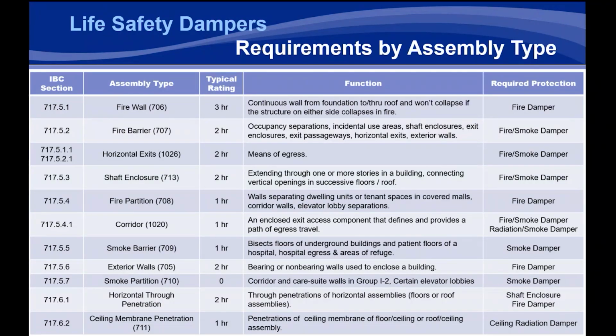So this is an overview of all of the different sections of section 717. We go through the different assembly types. And then when you see that assembly type, there's a number in parentheses. That's actually the section that calls out the requirements for that type of assembly. So whether it's a fire barrier in section 707 or a corridor in chapter 10, section 1020, that'll link you back to where the minimum requirements for that assembly are. There's a typical rating, so it's 3 hours, 2 hours, or 1 hour, and there's a function, and then required minimum protection or recommended protection that we have as we go through these different assemblies. So this is really just a cheat sheet. You don't have to memorize this. It's something that we can send out as a bit of a cheat sheet after the fact as well.